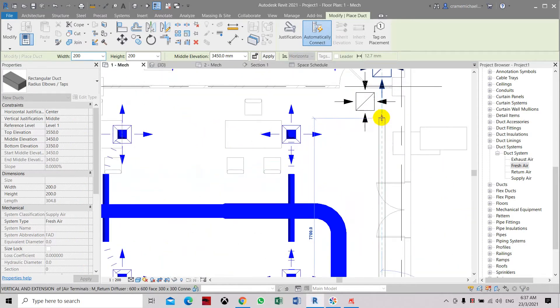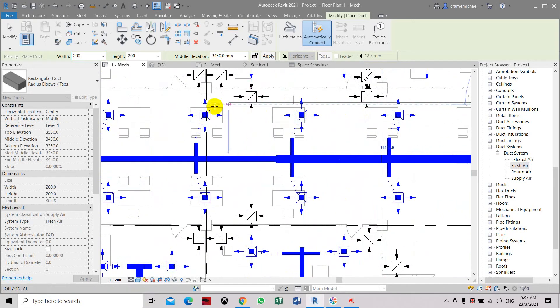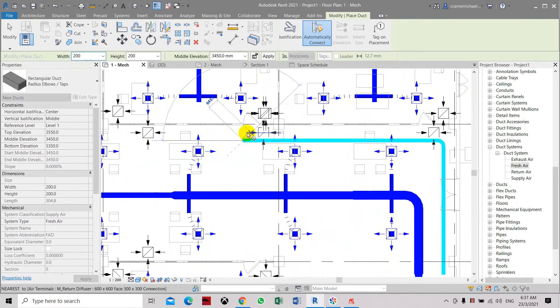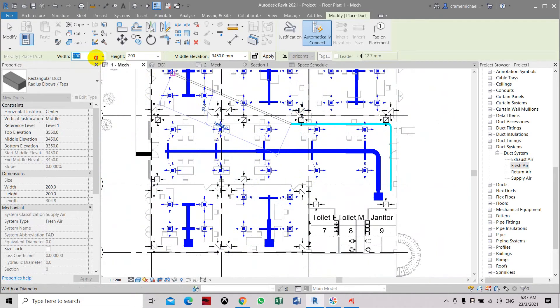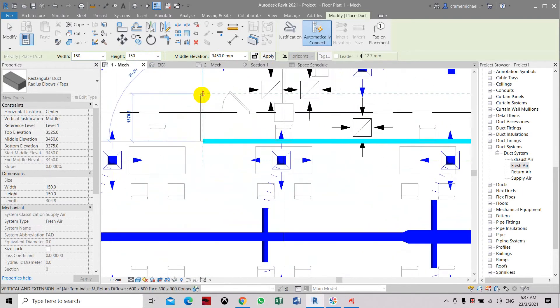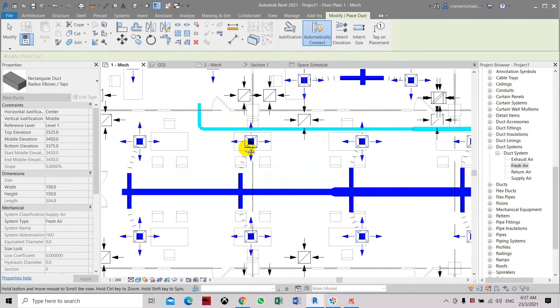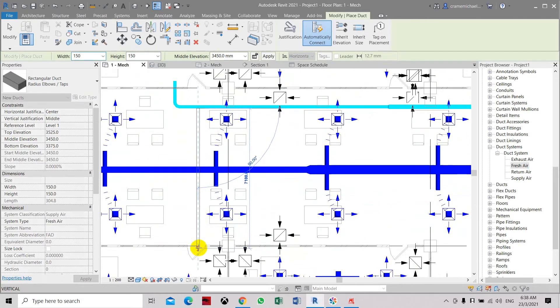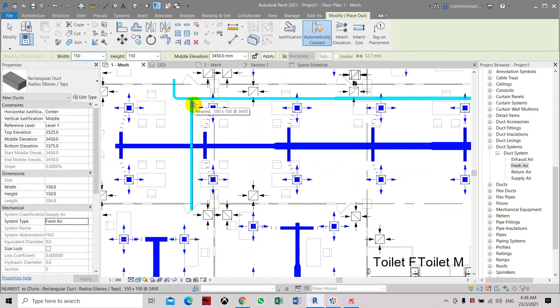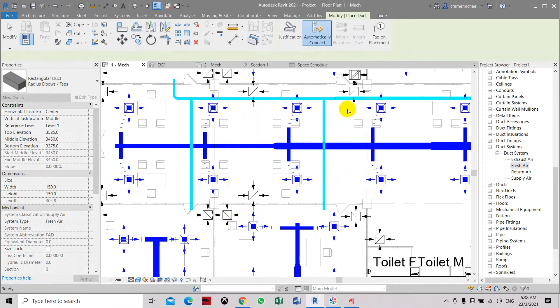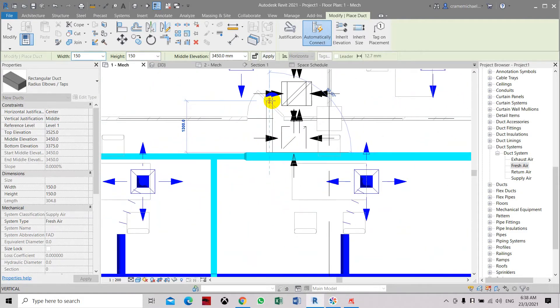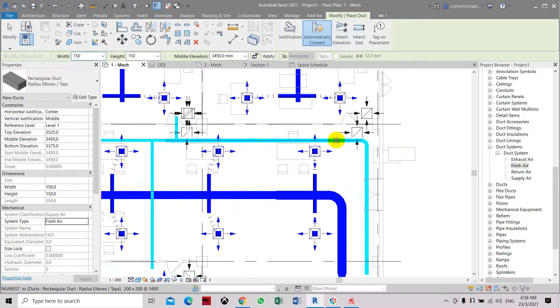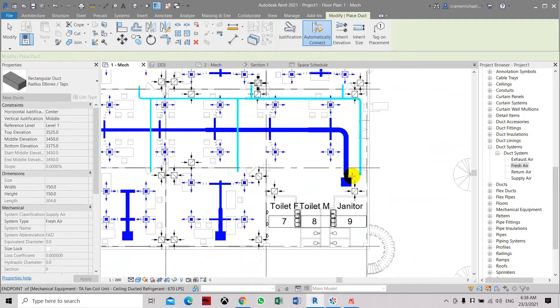Let's run the duct here. Once we have distributed to the three spaces, we're going to reduce it with 150 by 100 branches. One duct we can put inside the ceiling space, and another duct we can run up to this type and supply air from inside the duct. We can also duct somewhere using a 150 by 150 duct, or actually we can use 100 by 100. We also need to run one like this.